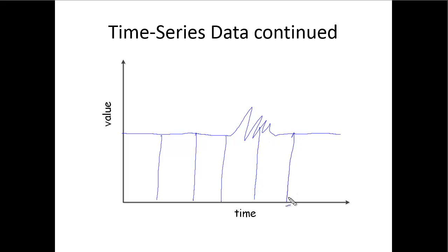Okay, so there's the values that I just took, and so what it looks like happened, and let me pull up a different color pen here, make it red. So what it looks like here is that it did this and then came up a little bit and then went back down. That's what I'm going to see when I retrieve the data out of my historian, and I just lost this information right here. So that's a problem.